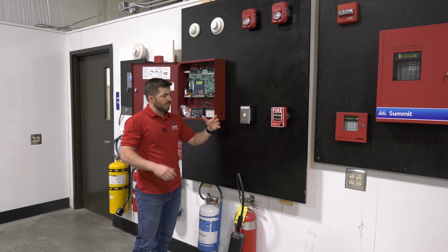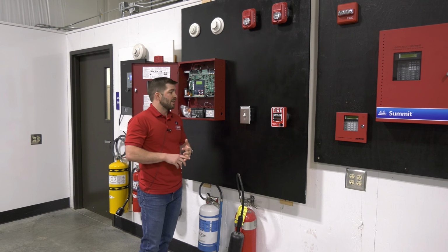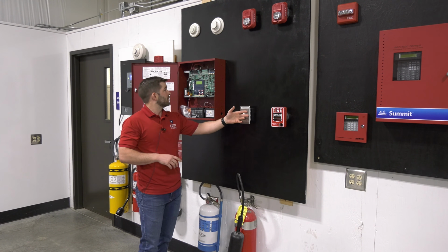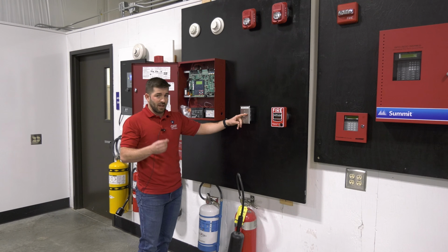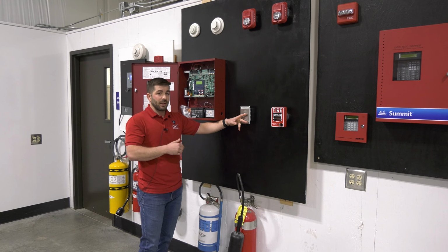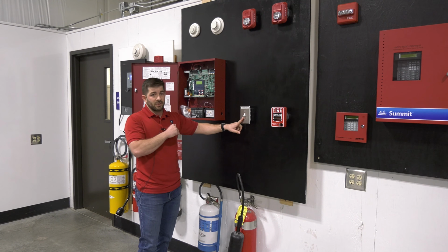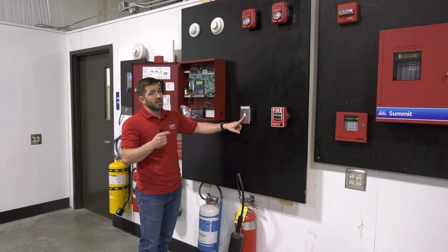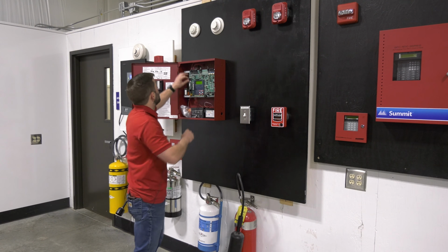Now you have a different type of supervisory. You have a latching and non-latching. If it's non-latching, that means like here, it's off normal condition, back to normal, and it clears itself. If it's latching, if I was to return it back to normal, you still have to go back and reset the alarm panel. But again, 90 seconds once that device changes state to annunciate a supervisory at the panel, and then once it clears, if it's non-latching, it has up to 90 seconds to clear at the fire alarm control panel.